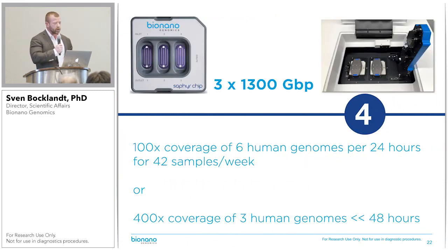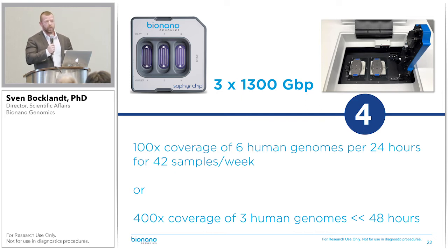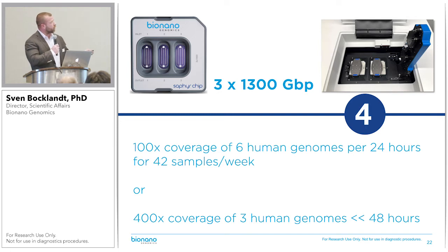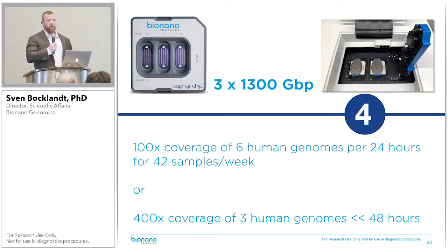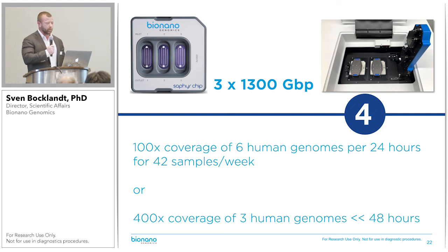That allows us to collect 3 times 1.3 terabase pairs of a human genome per run. Each of the three flow cell chips — two chips fit in an instrument — collects 1.3 terabase pairs. Our spec sets 48 hours, but in reality we see that more at 24–28 hours or so for three genomes.